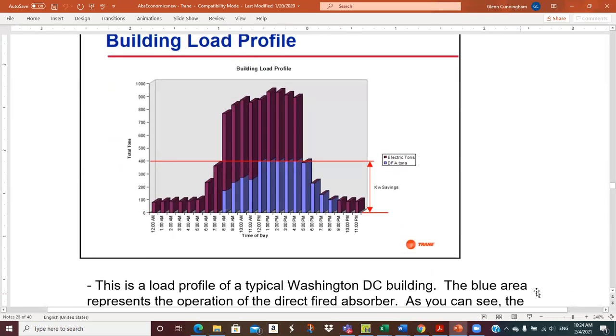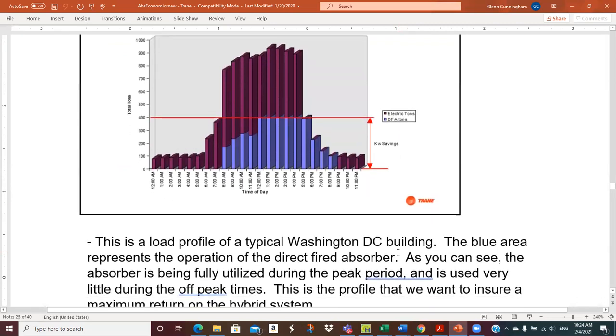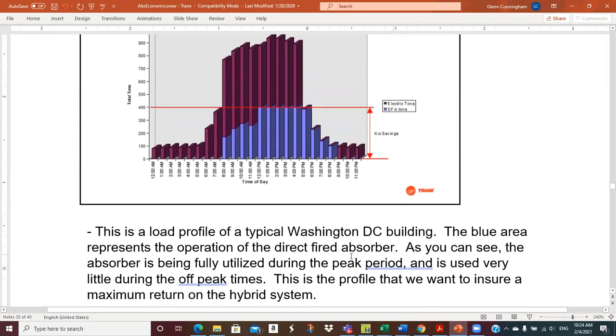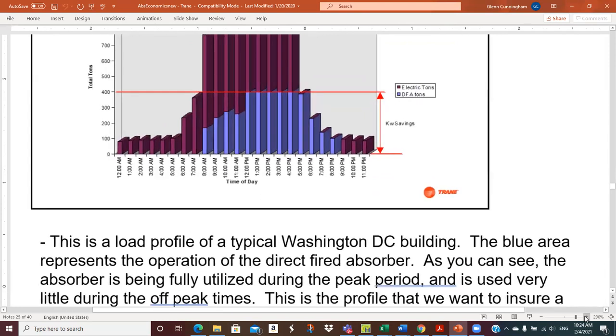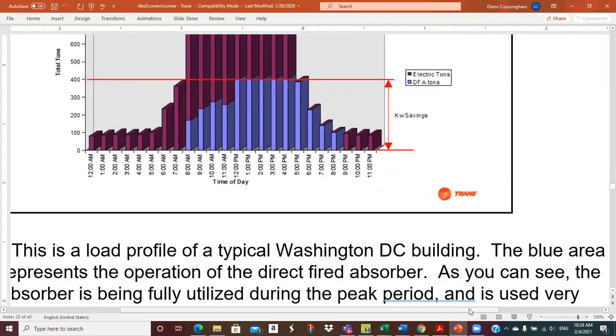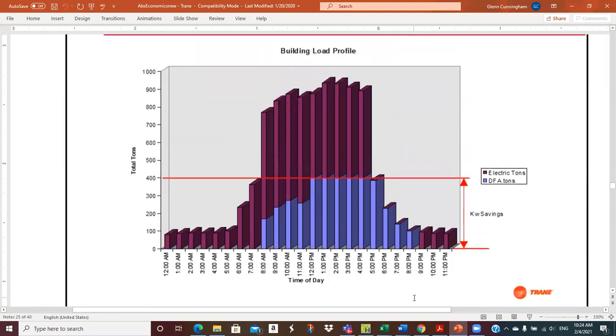Okay, let me make this just a little bit bigger. Let's read this here, make sure I get it right. The blue area represents the operation of the direct fired absorber. Okay, so this is the load profile for a typical summer day. So it's probably a design day or something like that. And so you see that over here in the heat of the day, 1 p.m., 2 p.m., 3 p.m., we're probably at 950 tons, something like that. We've got 1,000 tons of capacity. Looks like they did a pretty good job sizing the chillers. If this is a design day, they've got them just a little bit bigger than we need.